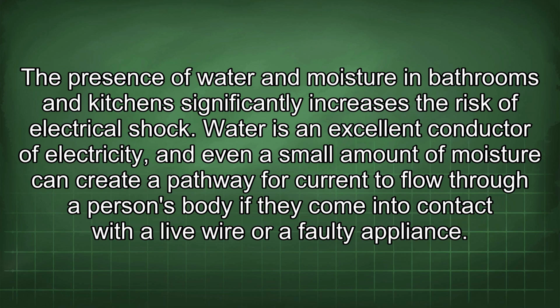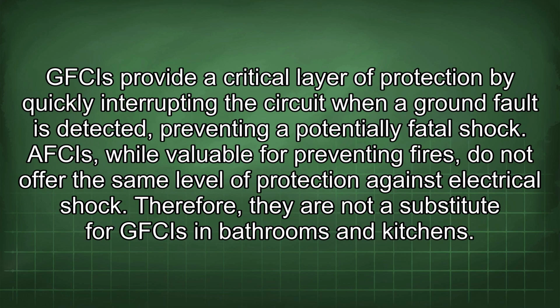Water is an excellent conductor of electricity, and even a small amount of moisture can create a pathway for current to flow through a person's body if they come into contact with a live wire or a faulty appliance. GFCIs provide a critical layer of protection by quickly interrupting the circuit when a ground fault is detected, preventing a potentially fatal shock. AFCIs, while valuable for preventing fires, do not offer the same level of protection against electrical shock. Therefore, they are not a substitute for GFCIs in bathrooms and kitchens.